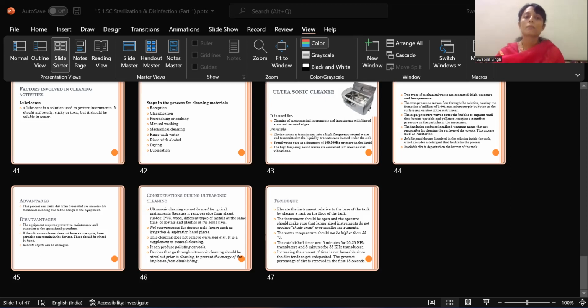Now the technique. Elevate the instrument first relative to the base of the tank by placing a rack on the floor of the tank. The instrument should be open and operator should make sure that larger size instruments do not produce shade areas over the small instruments or cover the small. The water temperature should not be higher than 65 degrees Celsius. The established times are 5 minutes for 20 to 25 kilohertz transducers and 3 minutes for 35 kilohertz. Increasing the amount of time is not feasible since the dirt tends to get deposited. The greatest percentage of dirt is in the first 15 seconds.